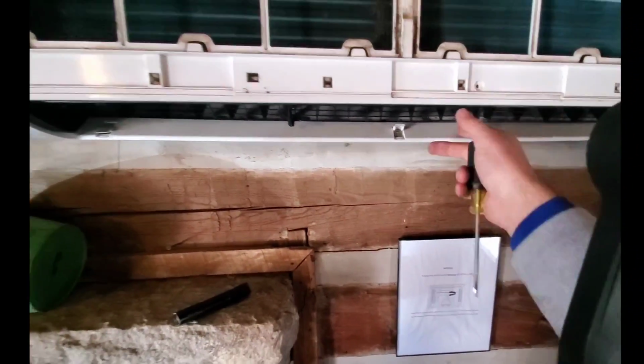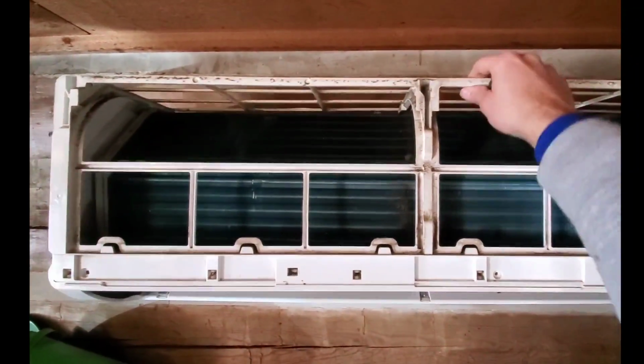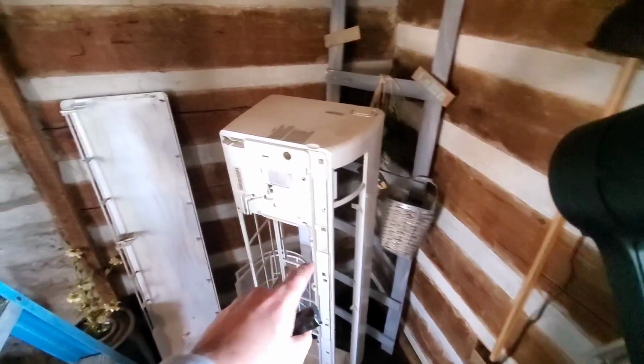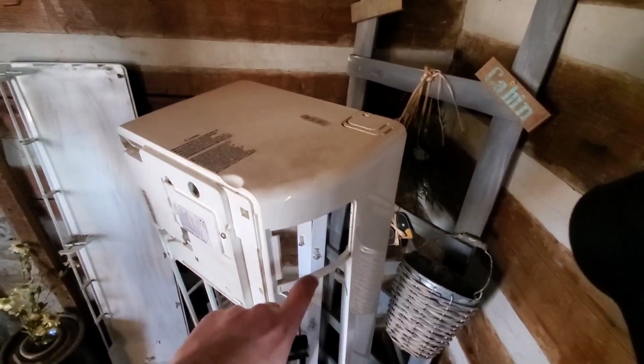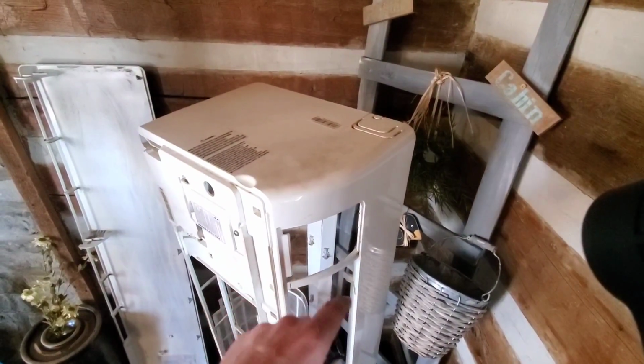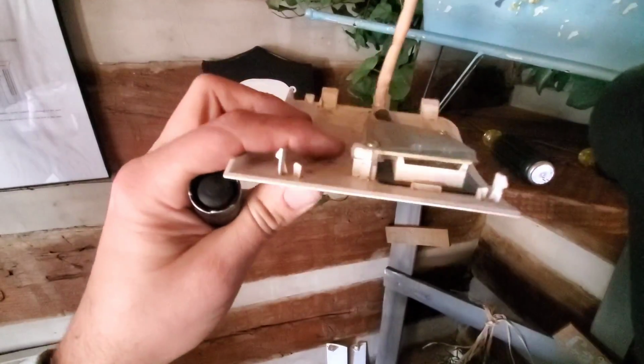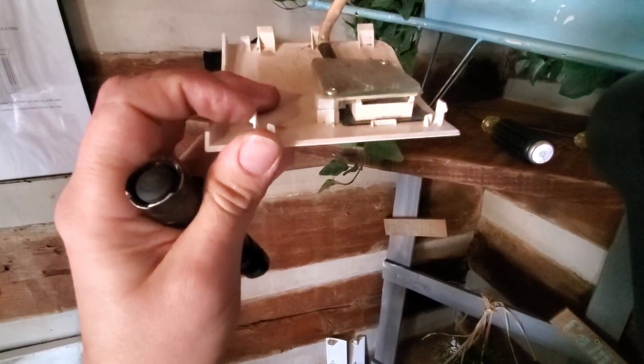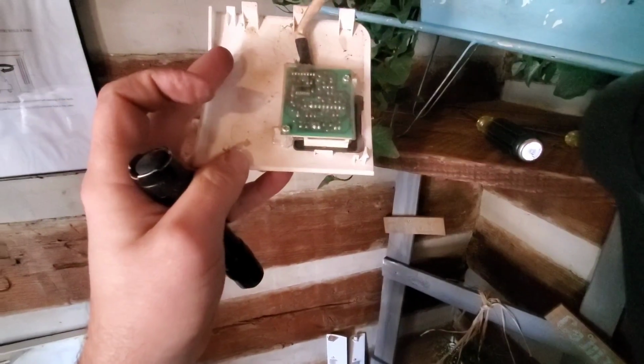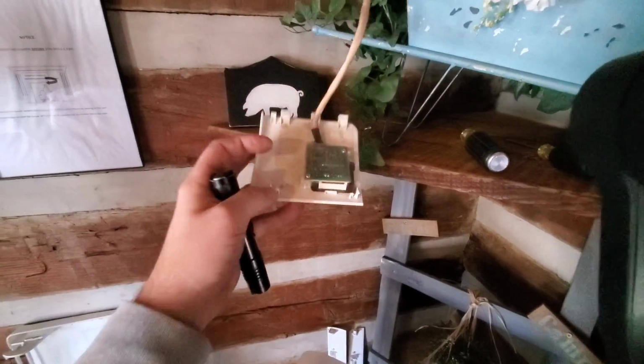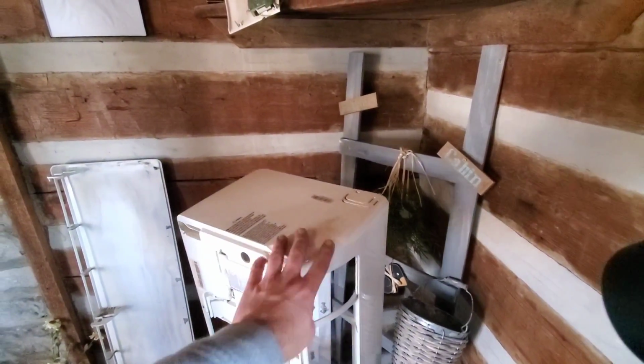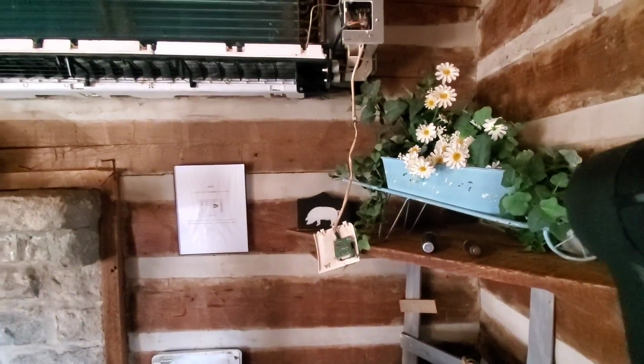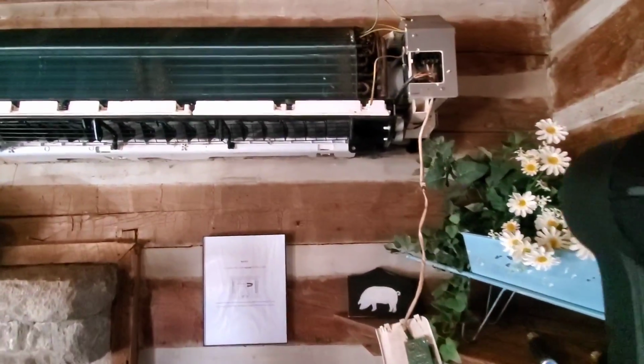Now we can take this off. So you're not going to really pull it from the bottom. It's going to go from the top. So we got the front cover off, and this is where the display was. The display literally just pops out. You can see that there's some clips there. This sets in place, and then there's what you have to pop out. And you can push this one this way and the other one from the back side when you get the cover out of the unit. Then just push it through and don't let it hang with the front cover on, because you could end up damaging the wire, pulling it out of the board.